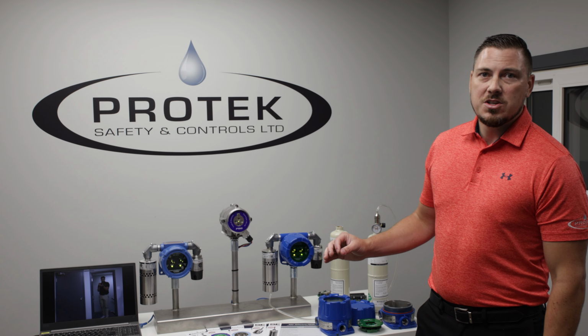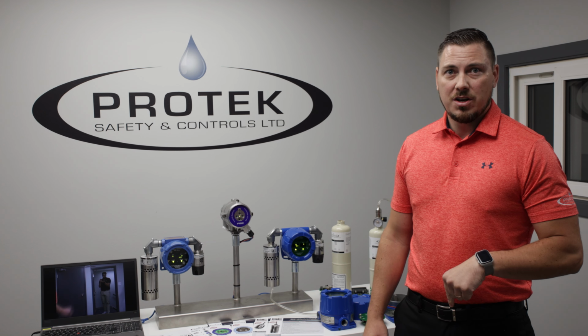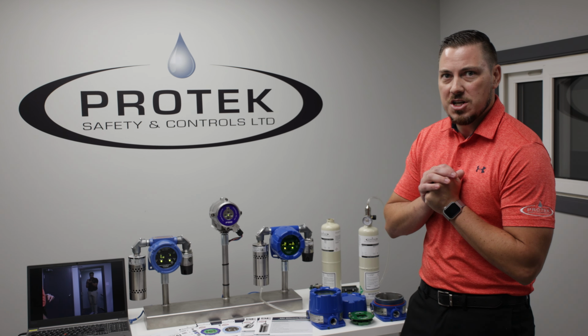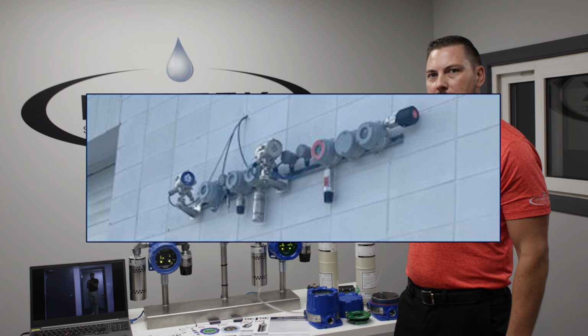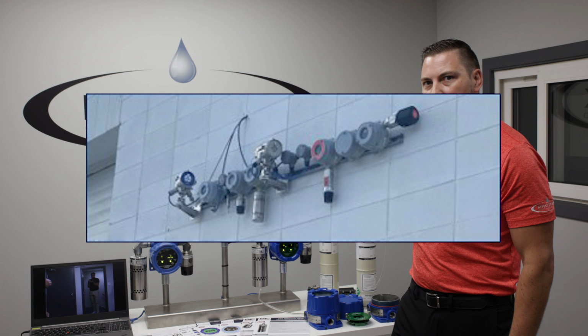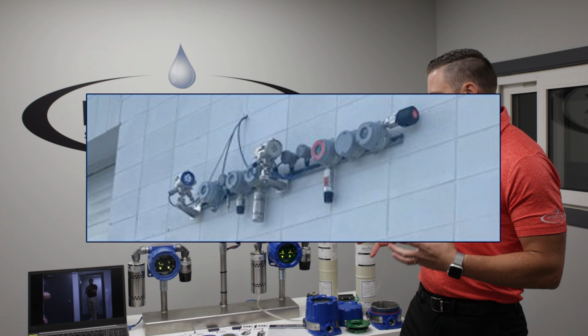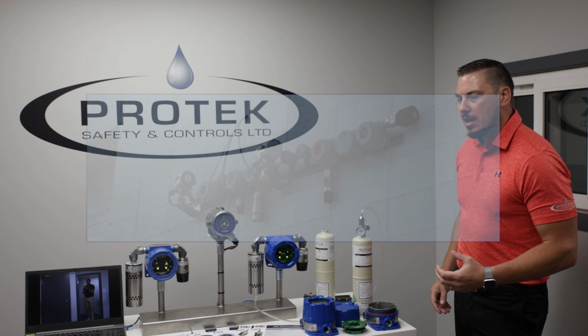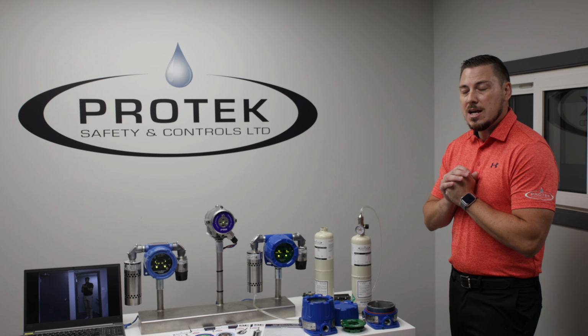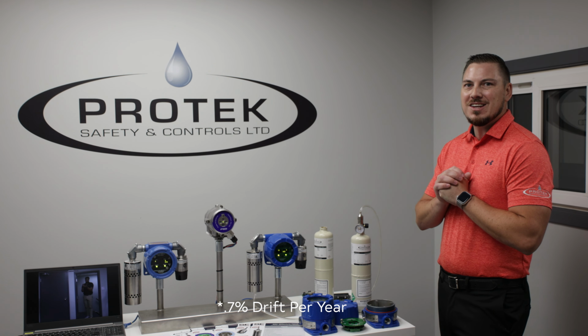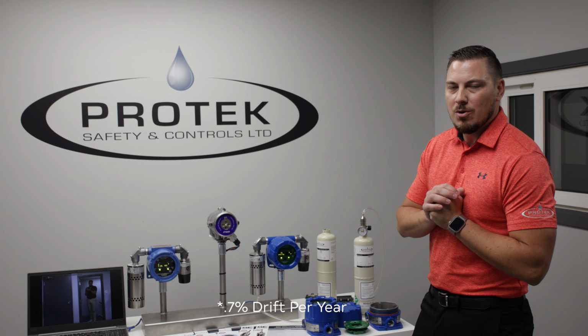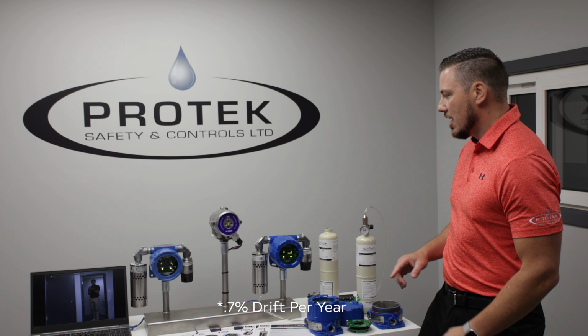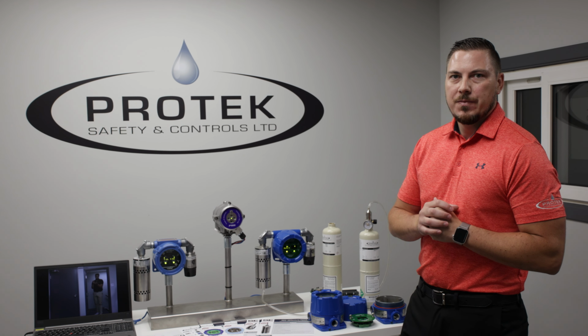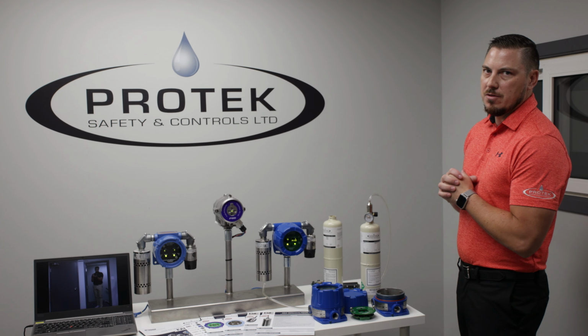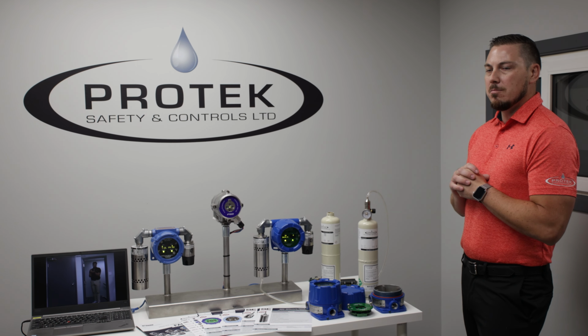This sounded too good to be true, so Protek at our facility here in Calgary, and you're welcome to come down sometime and check it out, we actually have units mounted out back that we've been trending the data for the past 4.5 years to see how this technology was going to work in real life applications. And we were blown away. 4.5 years in, we've seen a maximum 0.7% LEL drift with all the temperature swings, the delta, everything. Phenomenal. We have clients that have been using it throughout Alberta for the past 6.5 years and nothing but the best response.